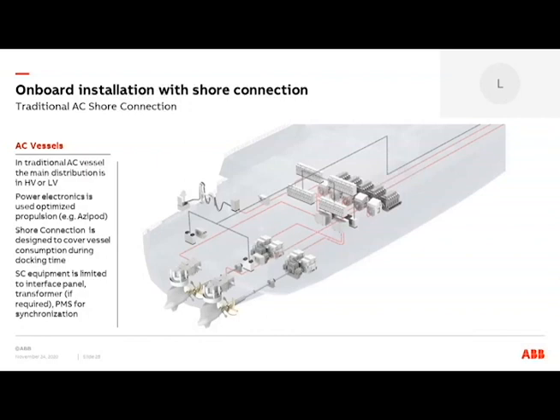In a traditional AC vessel, the main distribution is done in alternating current. Voltage can be high or low. Usually the standard voltages for distribution on board are 400 volts for 50 Hertz vessels, 440 for 60 Hertz, and 690, which is common for both 60 and 50 Hertz vessels.